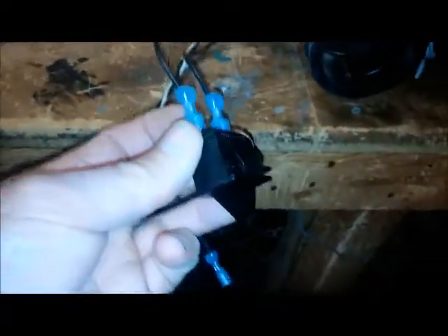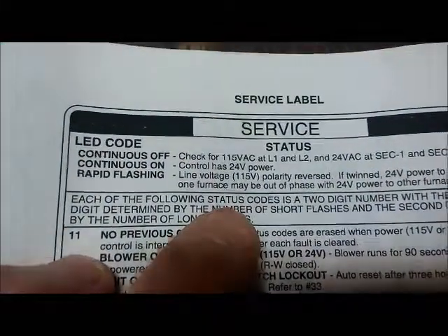We should have, if the door switch is pushed in, which is typically the bottom door in your furnace, usually somewhere in your furnace you're going to have a door switch, which disconnects the power. So we need power from the breaker to the board, which is going to go through a door switch. And then if all that is good, you're going to have an LED light flashing some sort of a code on this particular furnace. Every board and furnace manufacturer is going to be different. But this one, we have a light on, which indicates control has 24 volt power.